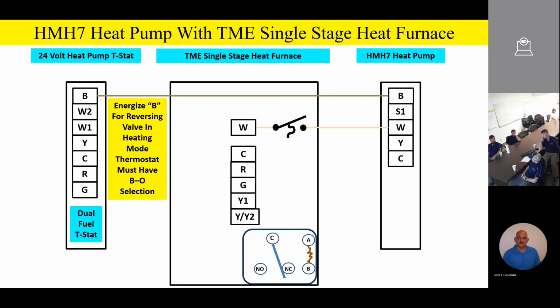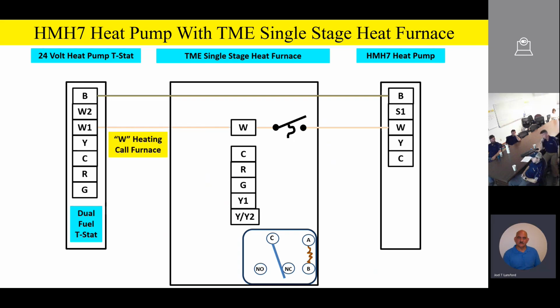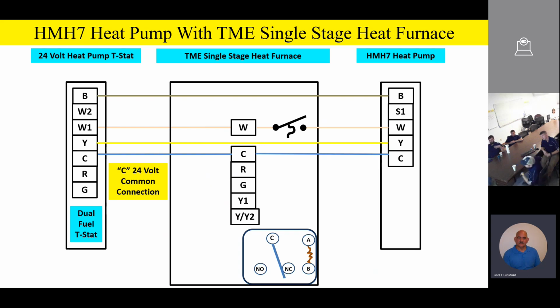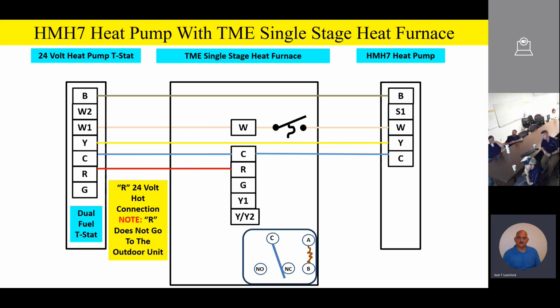And so W1 from the thermostat, because the TME is a single stage furnace, we only have one heating terminal. And so W1 will go to W on the furnace and then outside through that construction thermostat to W outside. Y stays the same all the way through. Common is all the way through again, just like we saw before. It's pretty straightforward. 24-volt hot goes to the indoor unit, but it does not go outside. Remember, that's important. It does not go outside.